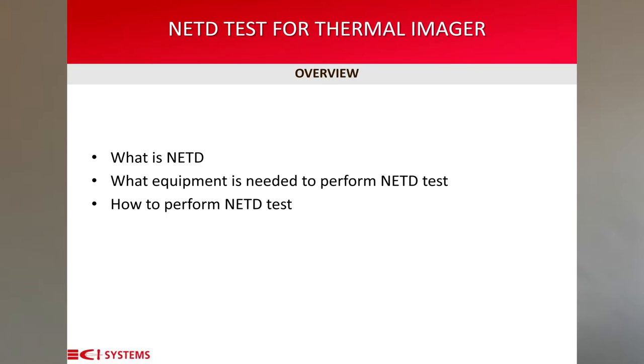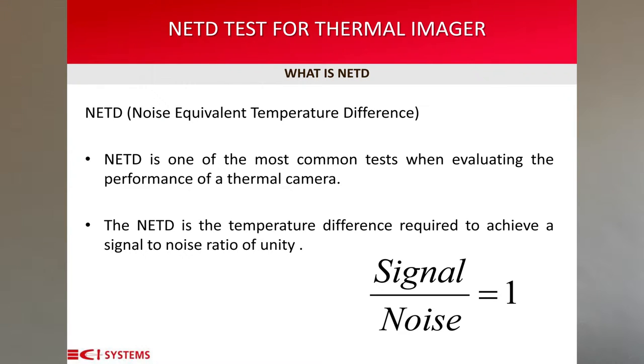All of these are integrated with our automated testing software. I will explain what NETD is, what equipment is needed, and how to perform the NETD test. NETD stands for Noise Equivalent Temperature Difference. It is the measurement of the smallest temperature difference that a thermal camera can detect in the presence of electronic noise.